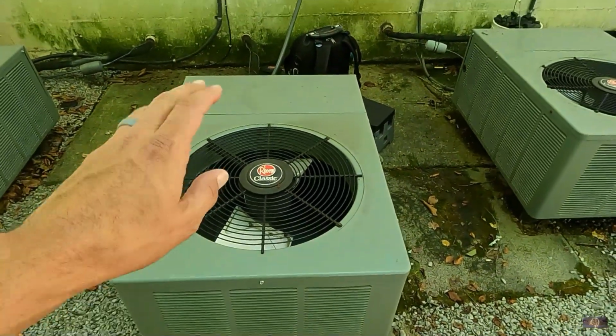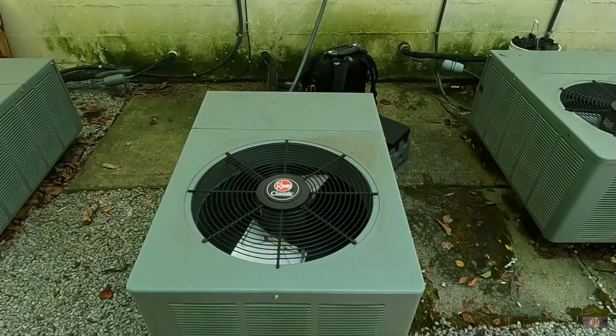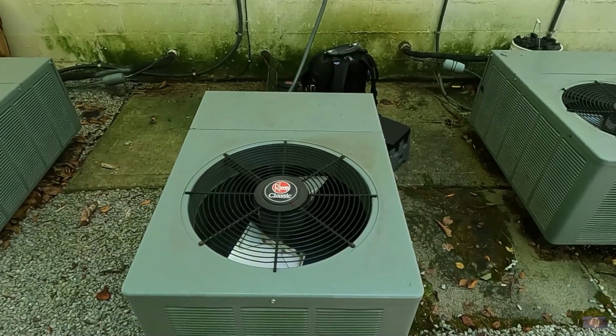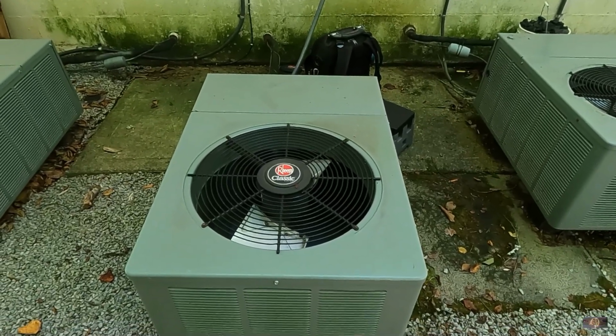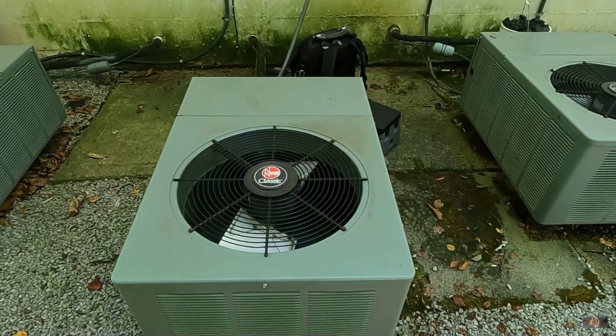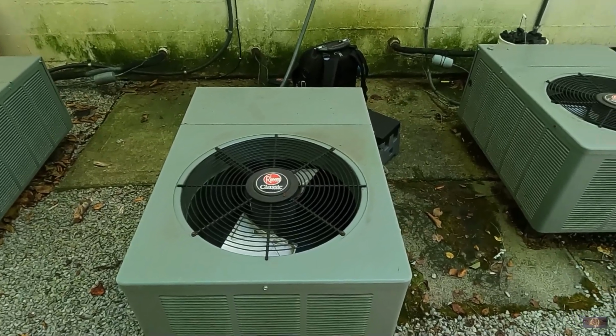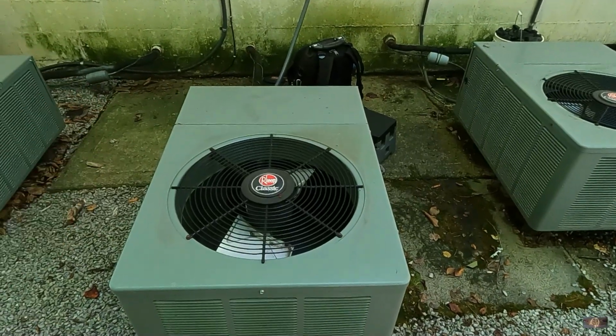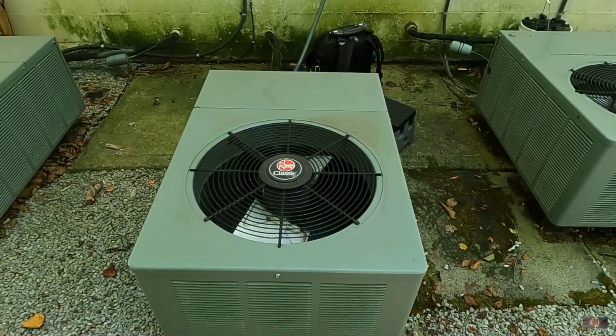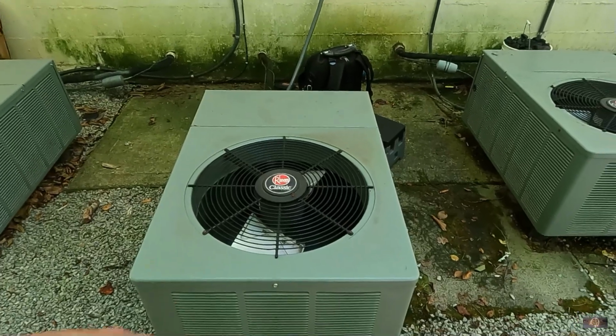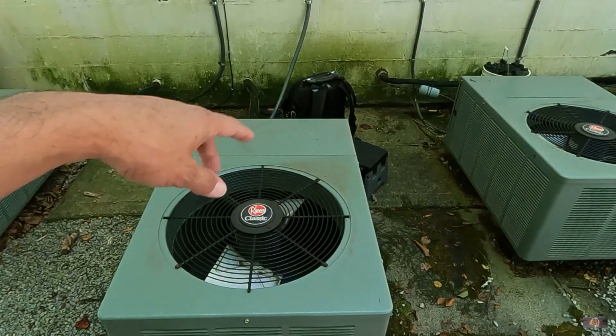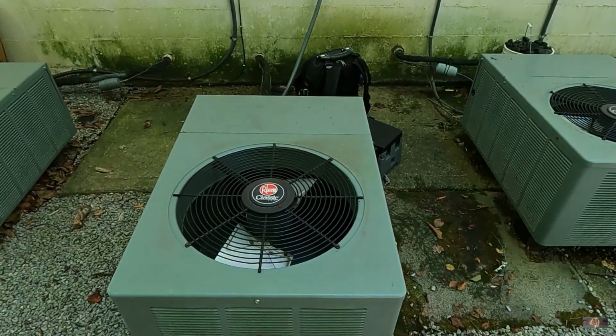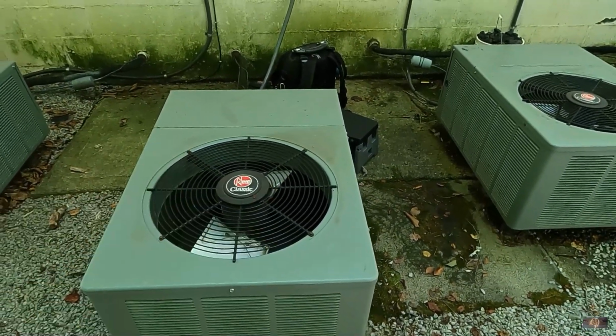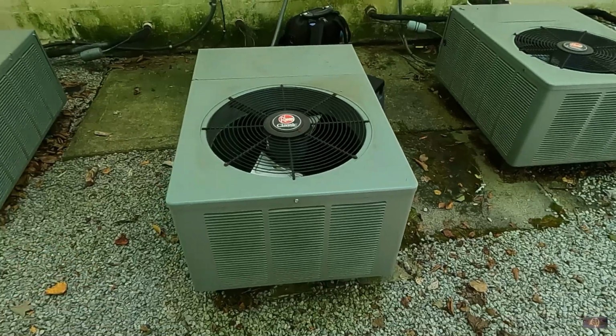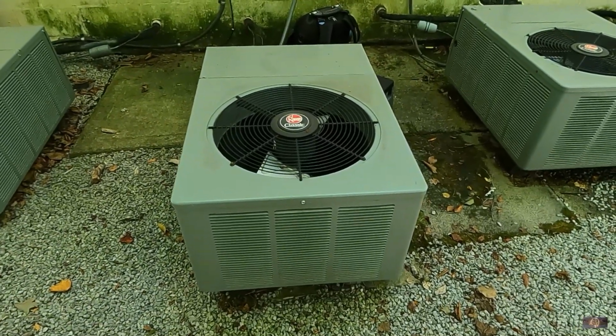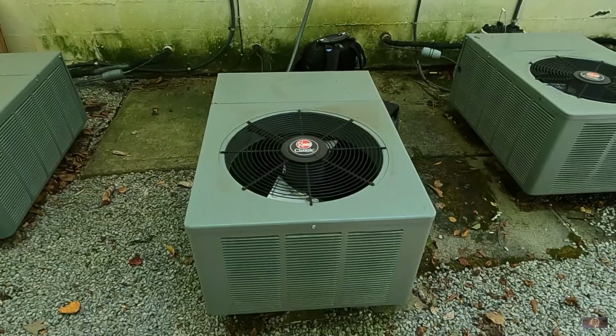So I'm going to go ahead and hook up probes to this. I always like to test it on a system first and see how it's doing, see if I see anything egregious on it that I need to address or let the homeowner or customer know about. So we'll just go ahead and hook up to it, fire the system, let it run for a little while, and see how it's doing, and then we'll take off the top, check the capacitor, of course pull the disconnect, check the contactor coil, scrub the whole unit down, wash through the coil. I'll take the sides off of it and wax it when I put it back together. I like to do a wax as well.